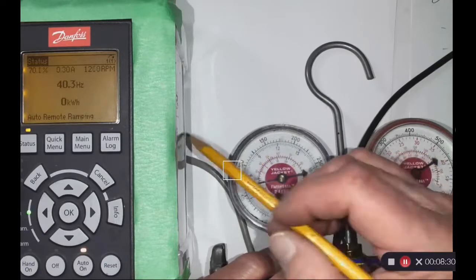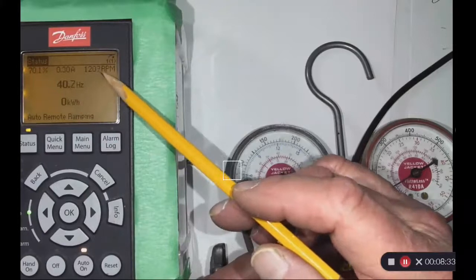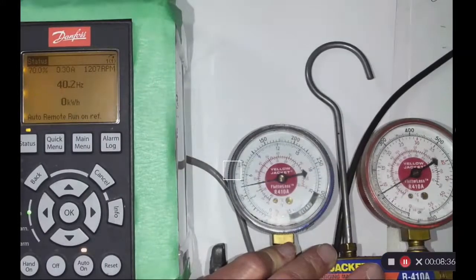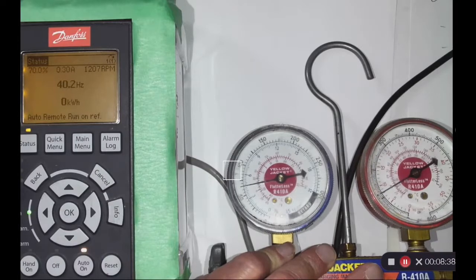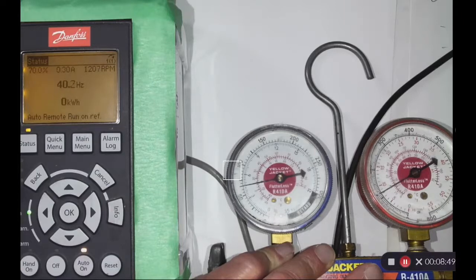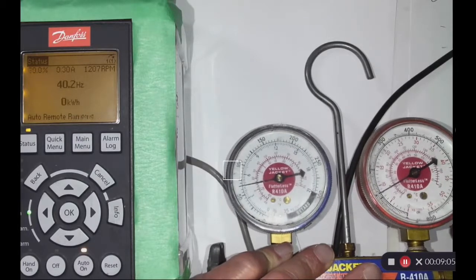And now the motor is up higher into its RPM. So that's going to basically try and control my head pressure per se. And don't forget, you have to use the correct transducer if you're doing higher pressure refrigerants. Even this transducer we're using would probably be well suited for superheat controllers and that kind of device on the low side. I know this transducer does not work with 407, 410A superheat controllers because the pressure is a heck of a lot higher.